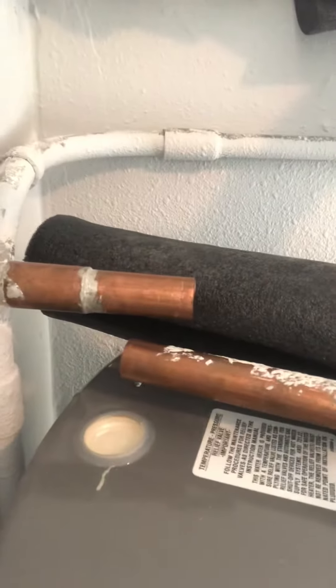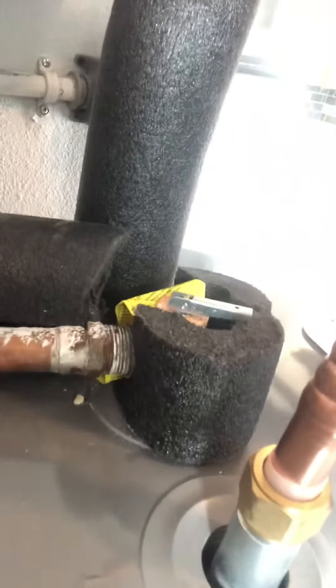that the drain line is leaking — that's one of the drains hooked up to the temperature pressure relief valve — it's dripping here. And notice as I look in the catch pan, there's about a quarter inch of standing water in the pan.